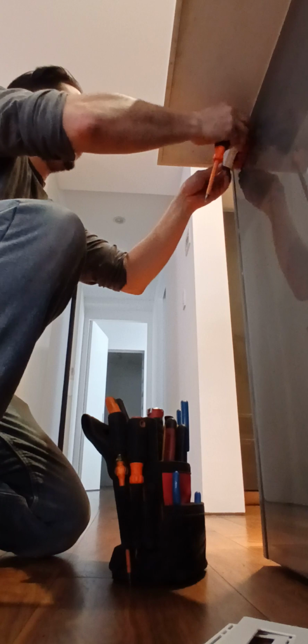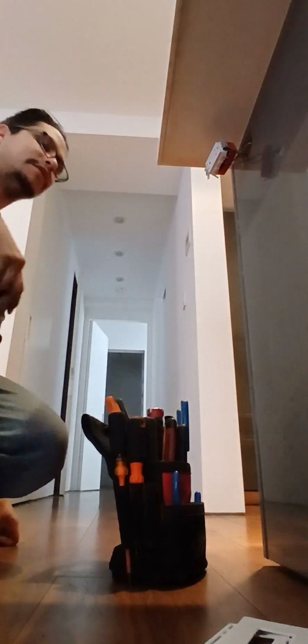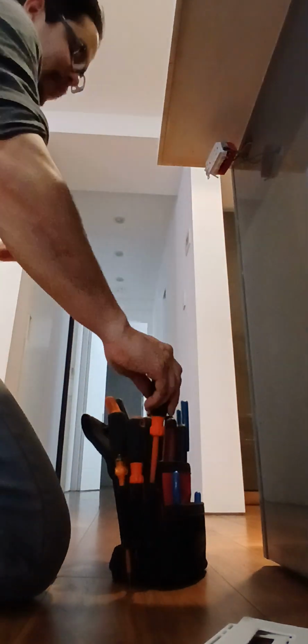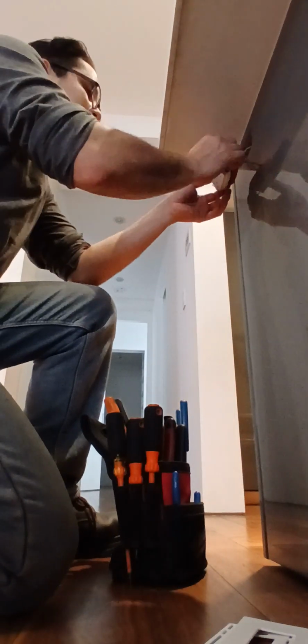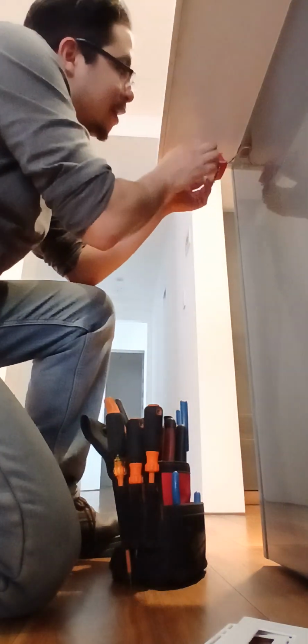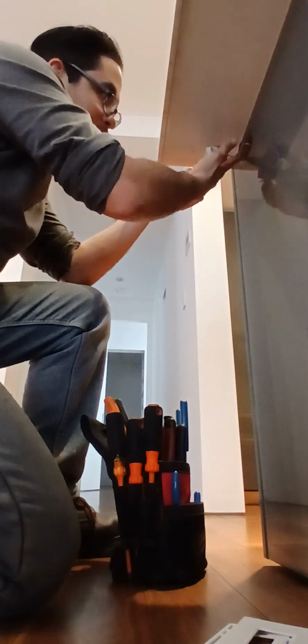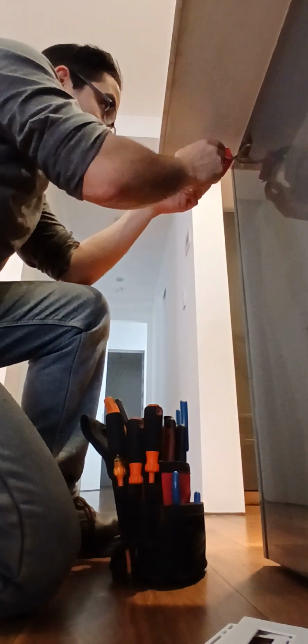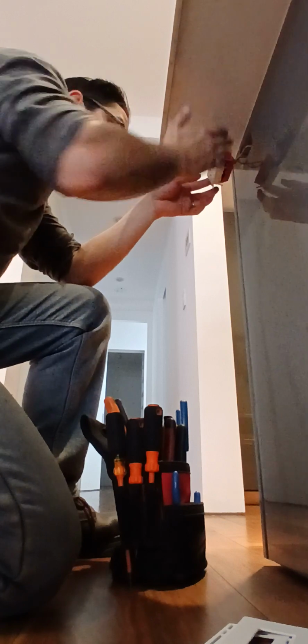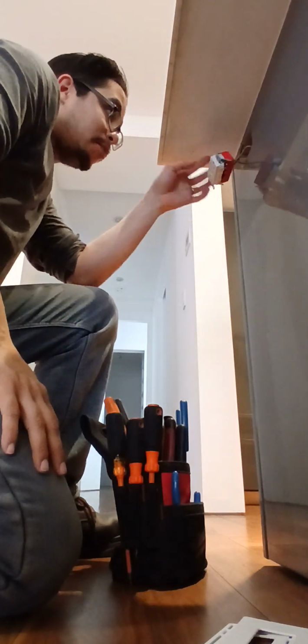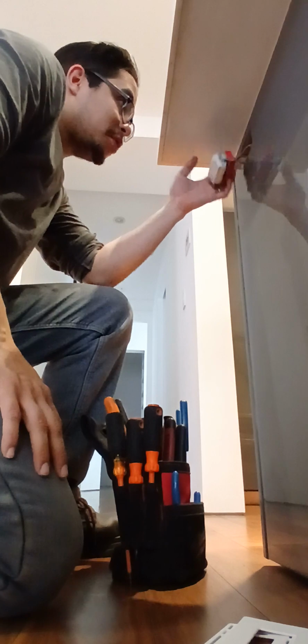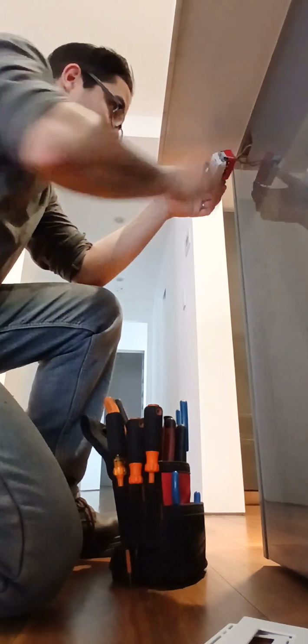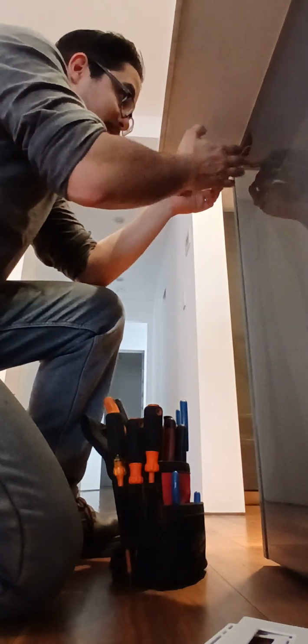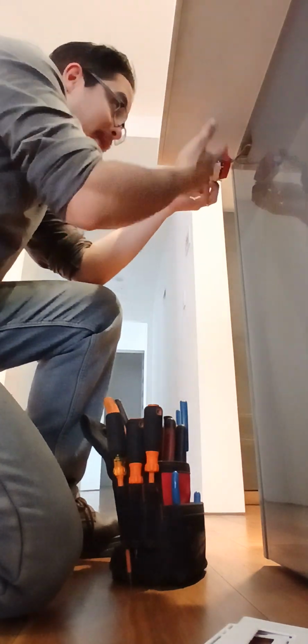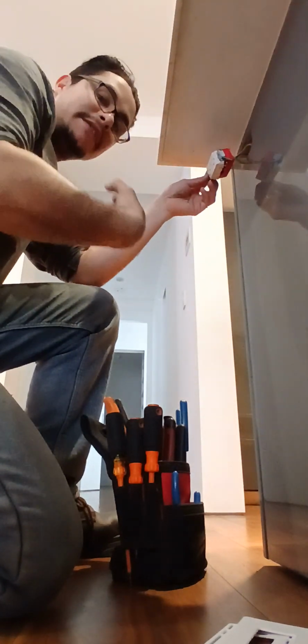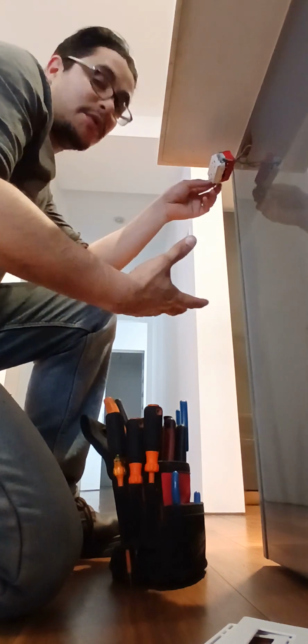A lot of electricians will say it doesn't matter, they just do it, but it's good practice. So okay, they bonded - they got an equipment ground bonded to the box. Perfect, because they have BX or Armor Cable 12-2, or most people call it BX. They don't have an equipment grounding conductor, so the jacket itself, the armor jacket, is listed as an equipment ground.